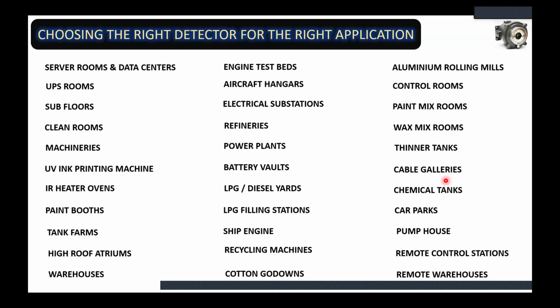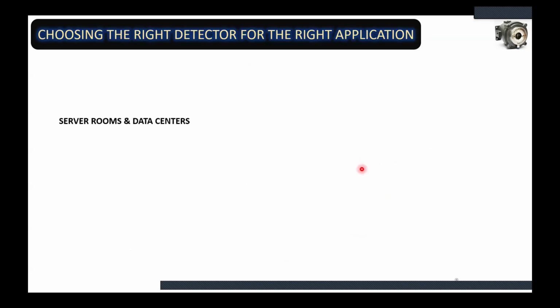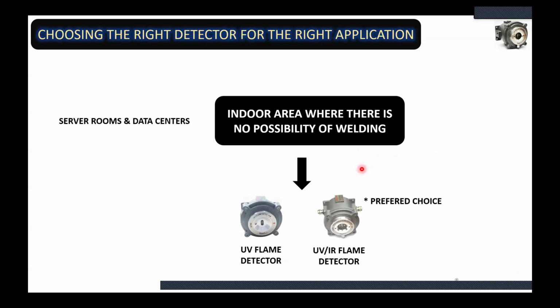So for the benefit of everybody, I have just listed a few applications where the flame detectors are used: server rooms, data centers, UPS, subfloors, clean rooms, machineries, different types of areas and applications. Which detector is suitable for which application? For server rooms and data centers, it is a purely indoor area where there is no possibility of any hot works like welding or other things. It is recommended to go with a UV detector, but the preferable choice would be a combination of UV and IR sensor, considering the better immunity to false alarms.